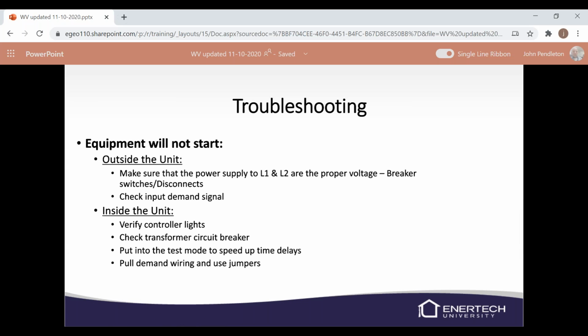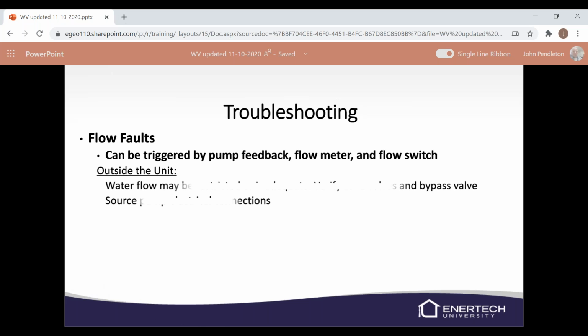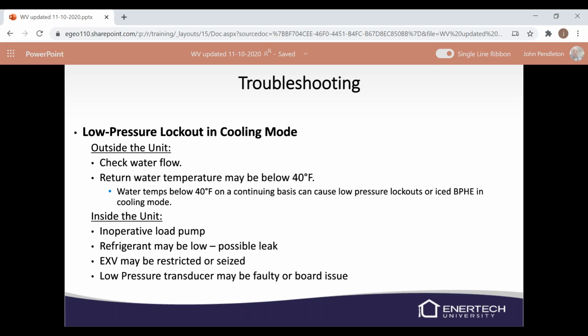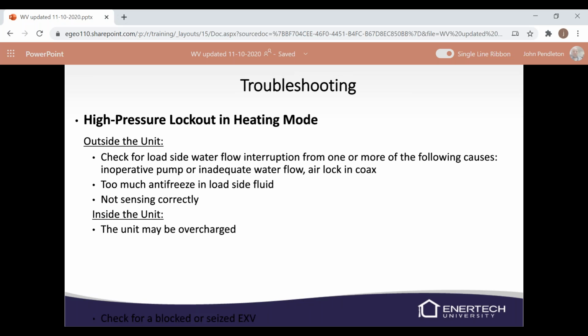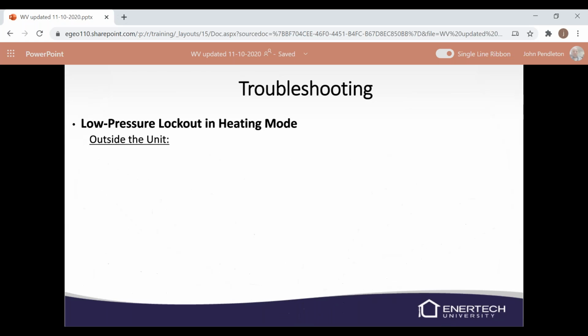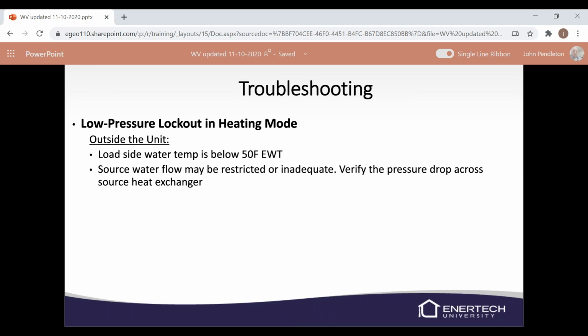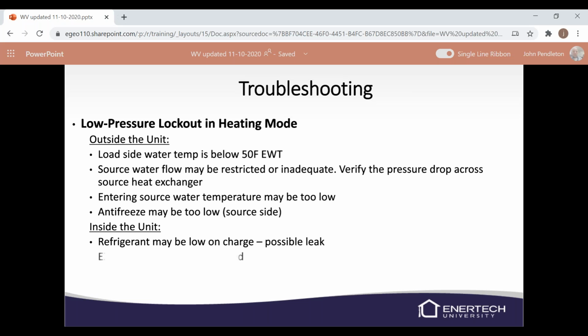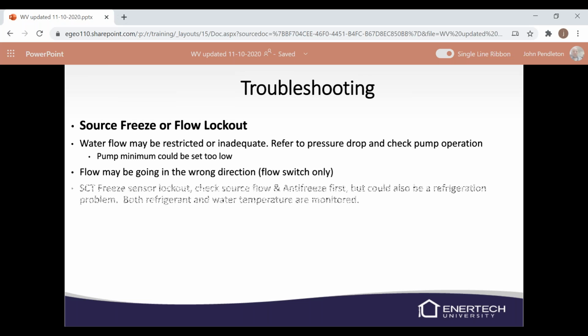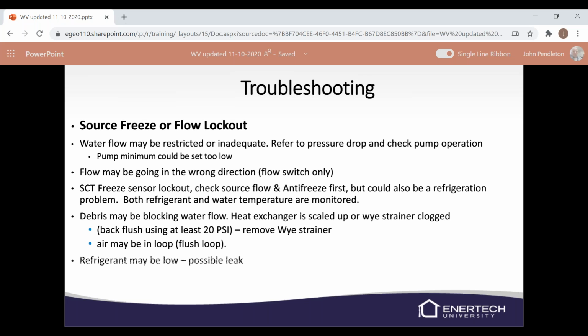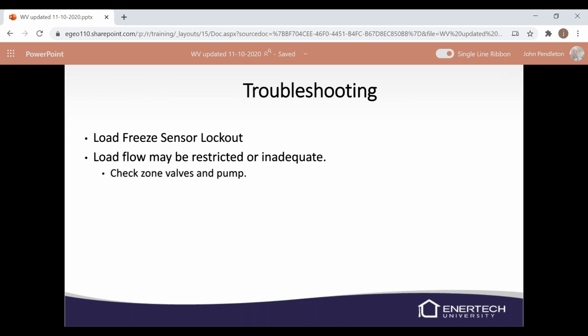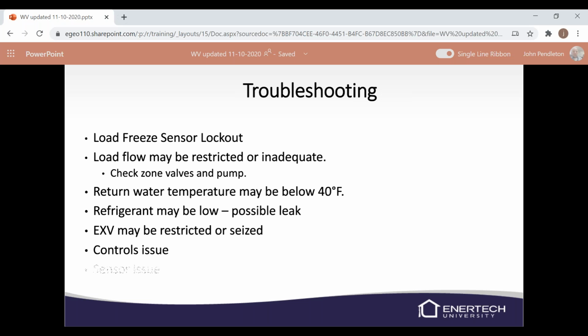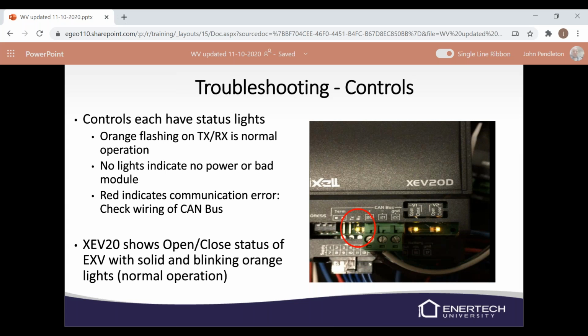So I'm not going to go through all these troubleshooting things here today. They kind of repeat each other, but flow is going to be your biggest issue. We don't have a real problem with expansion valves, reversing valves. We don't shift the reversing valve very often unless it's in cooling mode. And we don't really have any issues with the electronic expansion valves. Since they're driven open and driven closed, we don't have a problem with them getting stuck midway like we do on the thermal expansion valves.